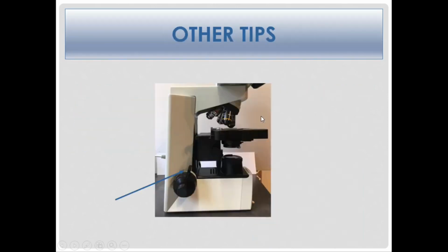Other tips. If you have been using your microscope for a while or simply over-tightened the focus knob, this tightening screw here can become loose. And as you try to focus, when you let go of the wheel, the focus slips, which is extremely frustrating. Some microscopes are supplied with a tightening ring here, which you just need to tighten up to resolve the problem. Others, you will need to use a screwdriver. But all good quality microscopes have a system for resolving this problem. If you can't find the mechanism to tighten the screw yourself, do not hesitate to contact your supplier and ask for help.